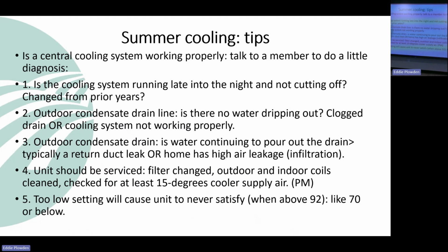In the wintertime, that's not an issue, and that's not going on at all. Is the unit serviced, filter changed, outdoor coils cleaned? And you need to have, in the summer, a 15-degree temperature difference. In the winter, it's more like a 20-degree temperature difference. So typically, if it's 70 inside return air, you need to be around 90 degrees for your supply air out of the heat pump itself. So a nice warm supply air.